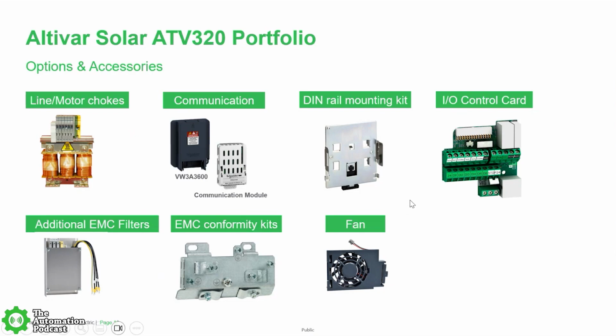Going back to the mining example, even though this is specifically for our 20 horsepower machine, we do have an application note for our Altivar 900 as well. They can go, I believe, up to 400 horsepower. So for some of these large mining applications, imagine not having to deal with the harmonics because you're tying directly into the DC bus. Harmonics happen at the input of the VFD, caused by the switching from AC to DC, and we're pretty much avoiding that by tying directly from the solar cell, not drawing the power from the grid. So just keep that in mind.